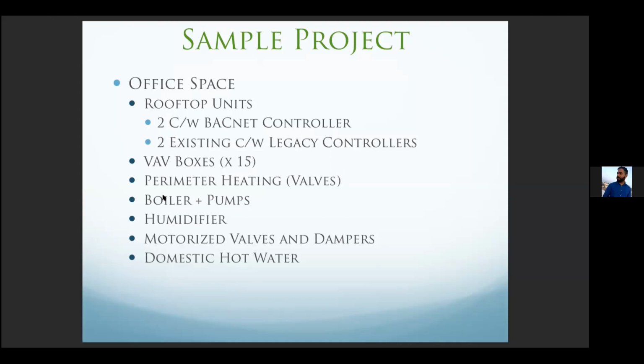Domestic hot water, typically it can be a standalone, it can be a 24/7 system because we need domestic hot water at any given point in time during the building. And sometimes if it's on the BAS, it may have some safeties. If the water gets too hot, it'll stop. And there's storage tanks as well to keep the hot water in there.